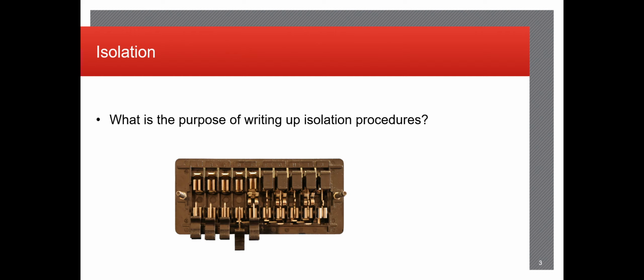Firstly, we're going to be going over the purpose of writing up isolation procedures. Isolation procedures are used to specifically avoid misoperations, damage to equipment, or risk of injuries to any personnel working in the field. The isolation of the equipment means either, on a large-scale sense, operating a breaker or switch to kill the load going through that part of the circuit, as well as isolating the secondary side, meaning the low voltage equipment in the control house or out in cabinets in the yard.